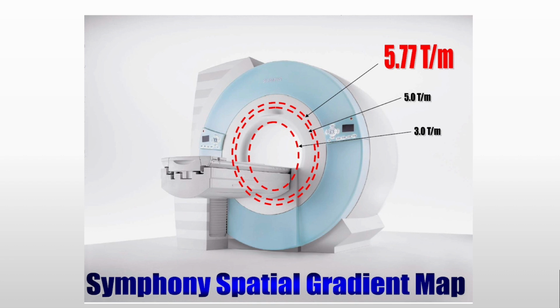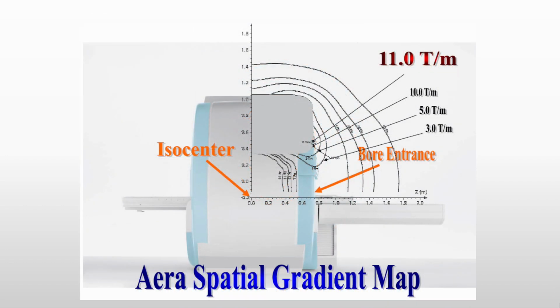When evaluating the ability to scan someone with an implant that has spatial gradient conditions, you need to decide if the patient will access the area with the highest spatial gradient. In this case, if you had a device that specified it could be in an environment that had less than 5 Tesla per meter or 500 Gauss per centimeter, you need to assess if the patient will actually be present just outside the bore, at the bore surface. This diagram is another interpretation of the data from Siemens. The contour lines are those provided by Siemens, and we have superimposed those on a magnet to show you where these maximum spatial gradients are located. You can see that the maximum spatial gradient for this magnet is on the bore surface at about 11 Tesla per meter.